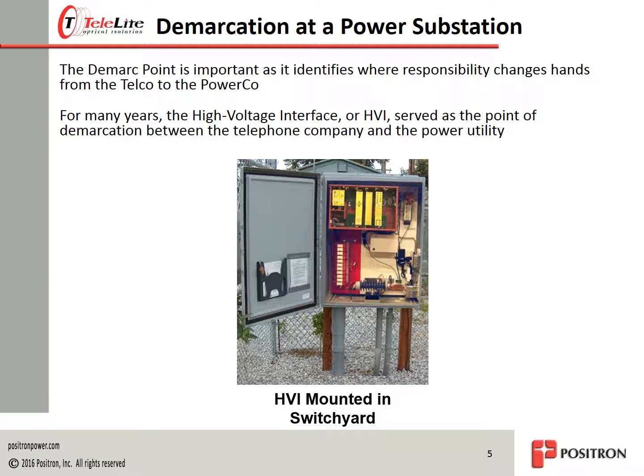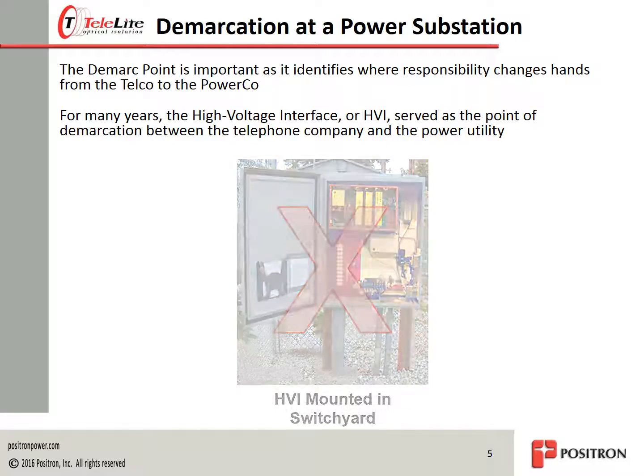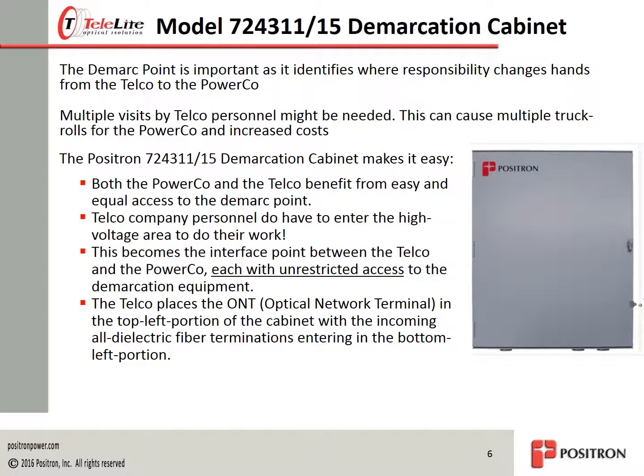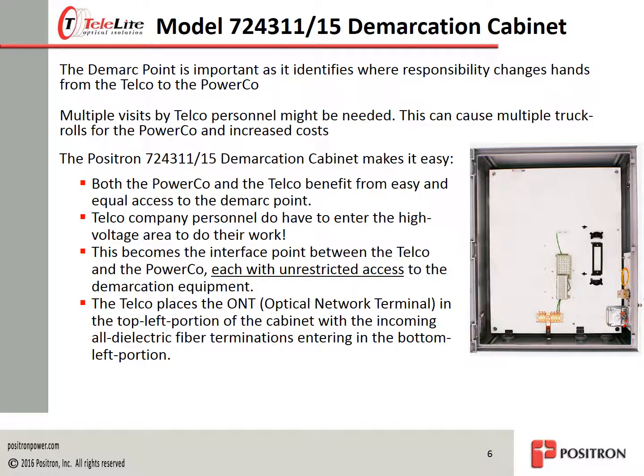However, when a substation is served by dielectric fiber, there is no HVI, on-grid or otherwise, in which to establish a demarcation point outside of the control house. Positron's demarcation cabinet offers an easy-to-manage and accessible demarc facility. When placed and bonded to the substation ground at the edge of the ground grid, near the substation fence, both telephone company and power company personnel can enjoy equal and unfettered access to the demarcation facilities.